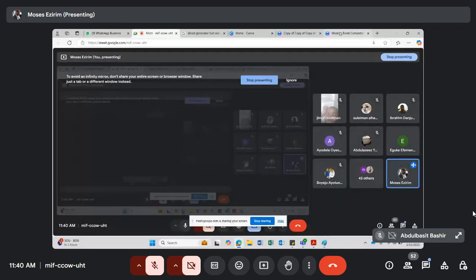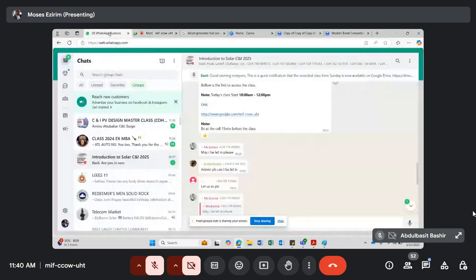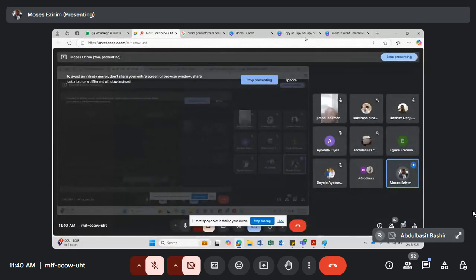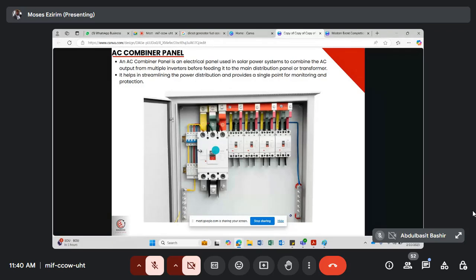The DC breaker should be a breaker that can withstand the voltage. If you are buying any breaker, you check the voltage. Remember, DC breakers come in different ranges of voltage. For DC voltage, the maximum is 1,500, so ensure that you get a breaker that can withstand that voltage. But for an AC breaker, if it is 3-phase, the voltage is just 400 volts. You understand? So there is a big difference.